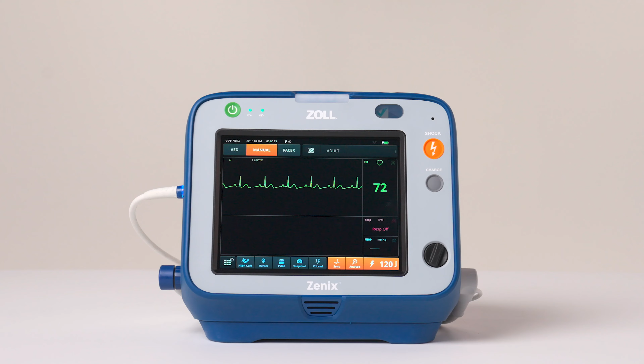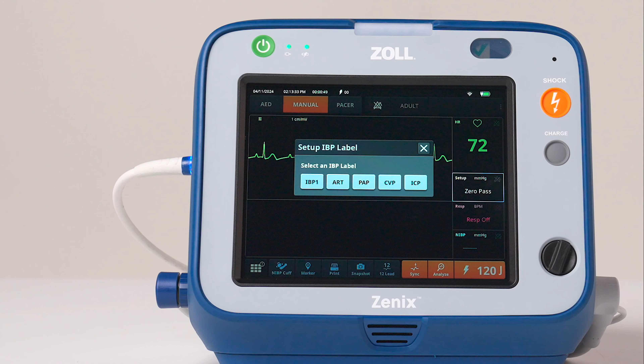Select the window labeled Setup to Zero Probe. In the Setup IBP window, select Zero Probe at the bottom. You will see the message zeroing while it is occurring. Once successful, a zero passed message appears.